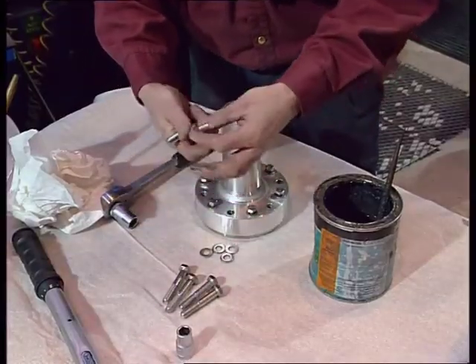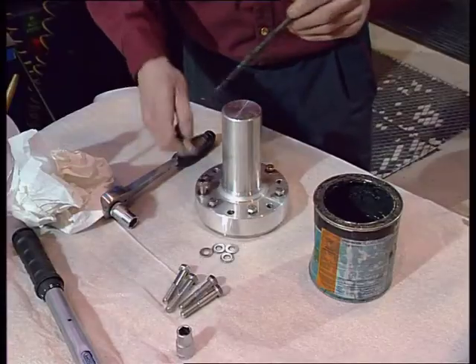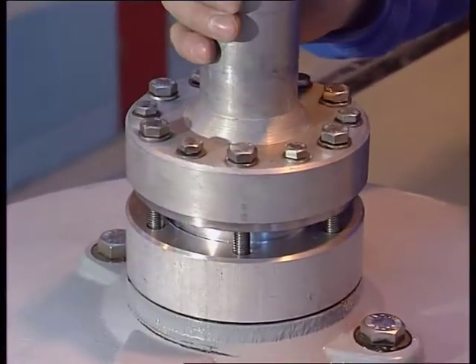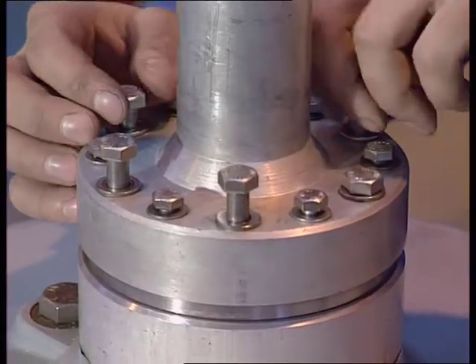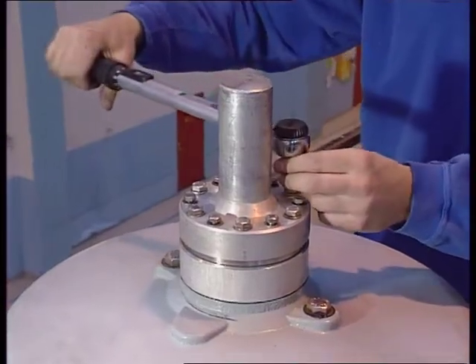Insert and tighten the M10 screws with plain washers which press the stud against the inner terminal. It's very important to tighten the screws crosswise and apply the recommended torque. Start with the M10 screws that are the electrical joint.